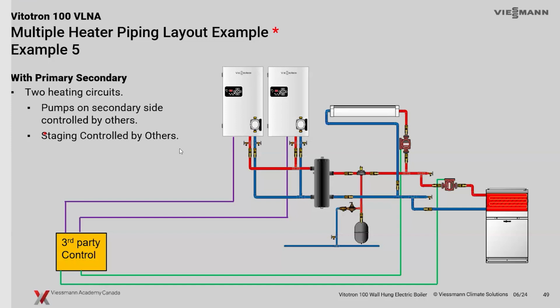Now, these boilers don't have, as some would expect with Viessmann, a cascade control for the boiler itself. With these little Vitotrons, we don't make an actual cascade control. Instead, you'd use a third-party control. In the West Coast here, Tekmar is a fairly popular control to use in that application. But there are a number of other staging boiler controls that are available out there.